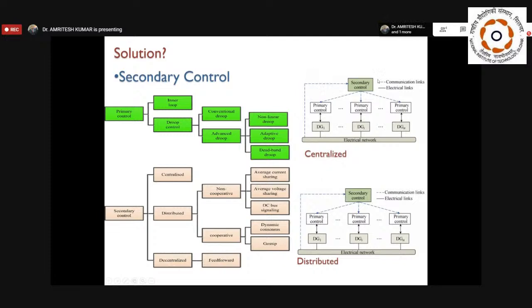Okay, so in the centralized controller there is one link for secondary control, and all are giving information. The secondary control is taking the data from the common DC bus, and accordingly it is giving commands to all primary control. So the problem is, if suppose this central controller is not working, then the information is not received by the primary control, and the whole operation will malfunction. Okay, because it's a single point failure. One point will fail, and the others will automatically fail.